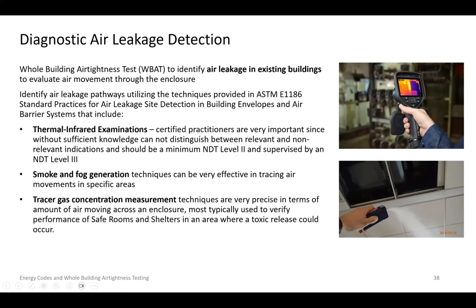I mentioned smoke and theatrical fog. A great way to look side. There's also tracer gas, which is more typically used for safe rooms in industrial settings. Oak Ridge is doing work right now to develop a technique that we can use on commercial buildings, because the benefit is not only see the leak, but you see how big or small the leak is. Right now, we can typically only identify the largest leaks, then we plug those, and then we have to keep working our way down, like fingers over the end of a water hose. So that's something to look forward to, but that could be 5 or 10 years out.